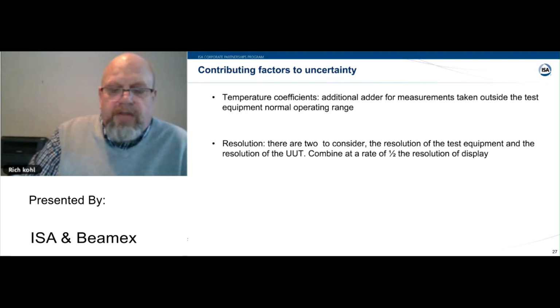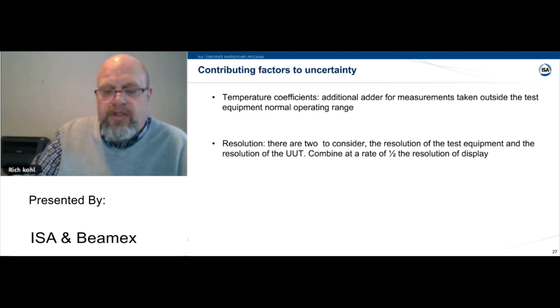I think he was using inches of water. So I guess the other thing here is you only consider the resolution of the measuring device. This could be the unit under test, or it could be your test equipment, or it could be both. And I think in Roy's case, it might have been both. No, he was using the transmitter, so it was just the test equipment display resolution that we're considering there. If he was calibrating something like a digital display or an analog pressure meter, you'd have to consider the resolution of both devices because they're both measuring.